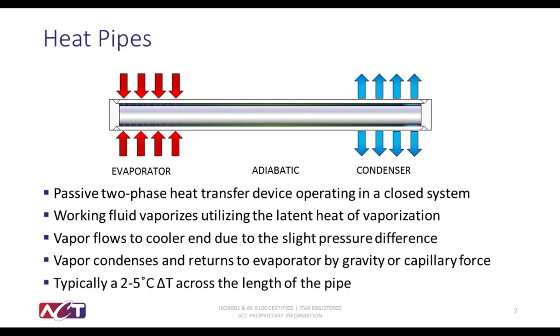Heat input into the heat pipe in one location causes that working fluid to vaporize, travel axially down the pipe, and then condense into the pipe wall in a cooler location, letting off its heat. That fluid is then pumped via that wick structure back to your evaporator. This is a completely passive solution that requires no additional energy input, yet moves a tremendous amount of heat from one location to another. A properly designed heat pipe will have about a 2 to 5 degree delta T across the length of this heat pipe and has extremely low thermal resistance.